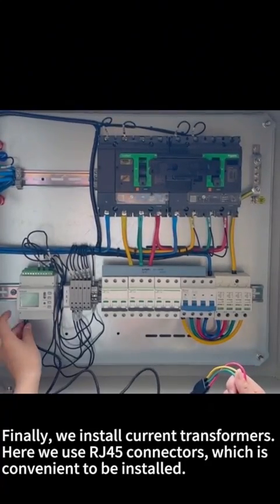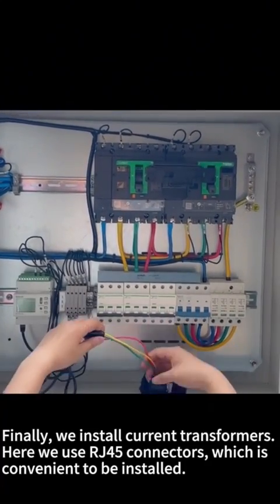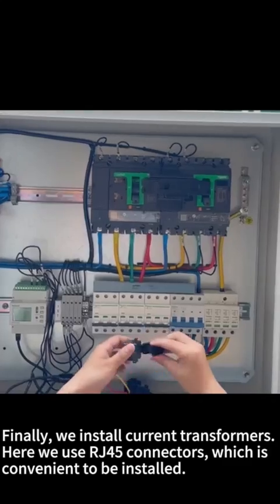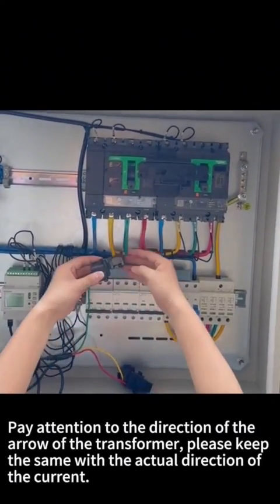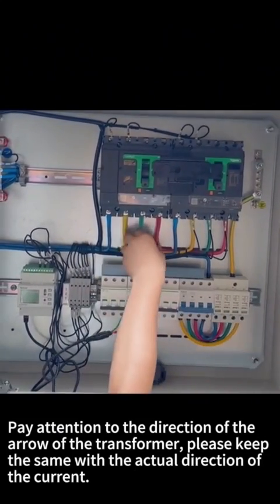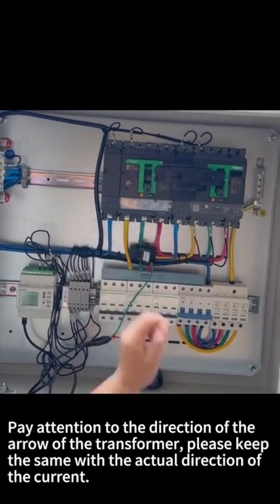Finally, we install current transformers. Here we use RJ45 connectors, which is convenient to be installed. Pay attention to the direction of the arrow of the transformer. Please keep the same with the actual direction of the current.